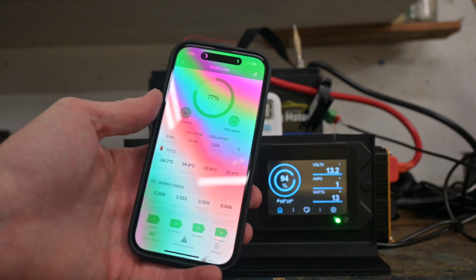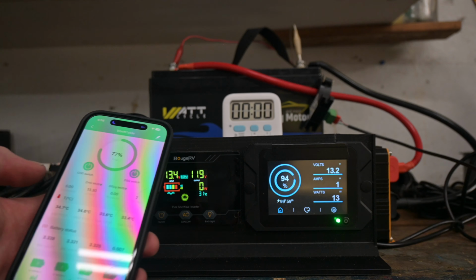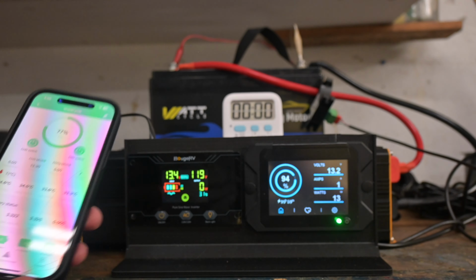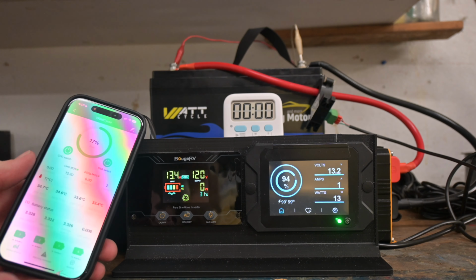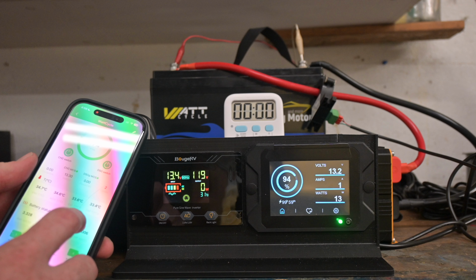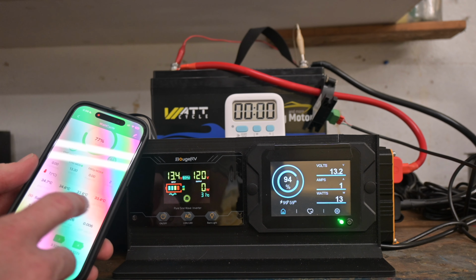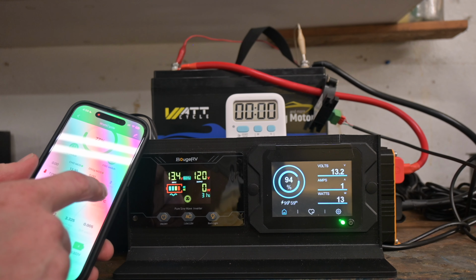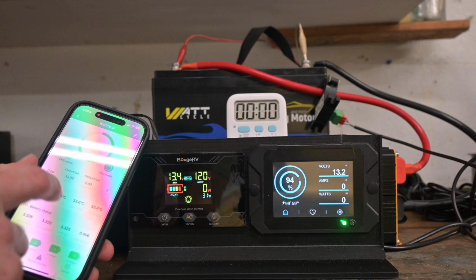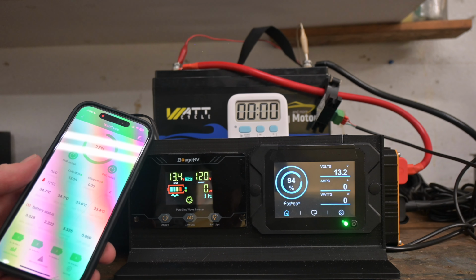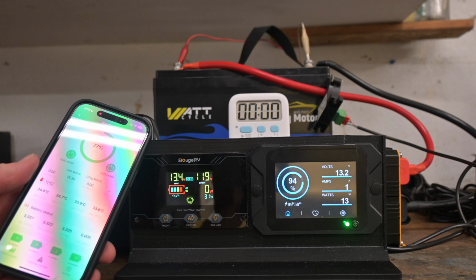So what we're looking at here is the battery's at 77%. You can ignore this one, it's not calibrated for this guy. But what we've got is our battery status, the temperature of each of the cells, total voltage, current's at 0, and 2 cycles on the battery so far. Charge is on, discharge is on, and we're at 77%.